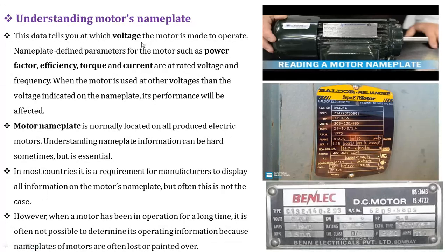Next one is understanding the motor's nameplate. This data tells you which voltage the motor is made to operate at. Nameplate defined parameters for the motor such as power factor, efficiency, torque, and current are at rated voltage and frequency.